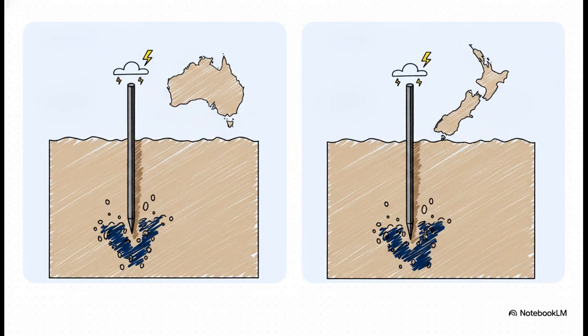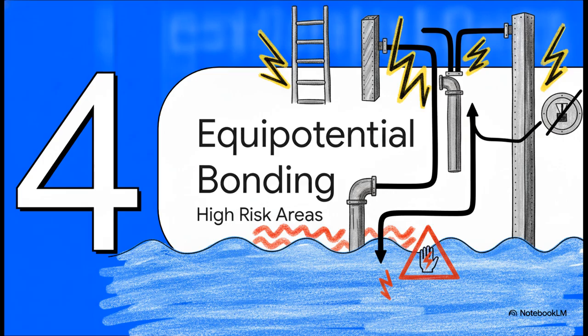Why the difference? Well, Clause 5.3.6.4 dictates the electrode absolutely must maintain effective contact with moist soil that isn't subject to excessive drying out. Deep, moist soil gives you that critical low resistance necessary to dissipate electrical energy safely away into the earth. Moving on to Section 4, Equipotential Bonding, Water, Electricity, and High Risk.